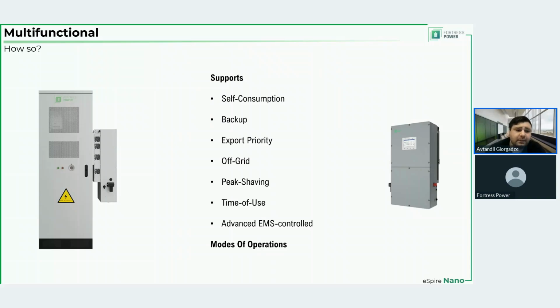It also supports advanced EMS controlled operation in conjunction with time of use. So you can have standard time of use. Standard time of use would be 6 charge intervals and 6 discharge intervals, and you don't need the Pro package for it. But in advanced EMS controlled operation, you can tailor the system for even more complex peak shaving and time of use applications, and you will require additional hardware for it.